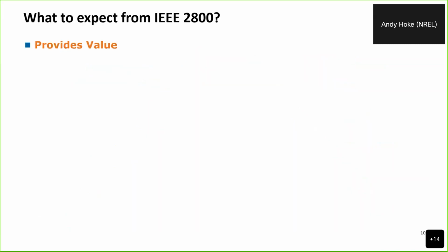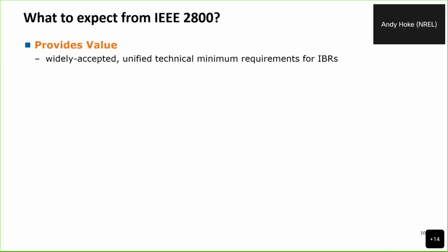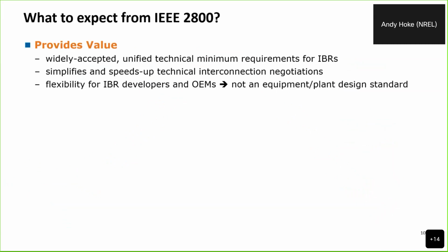Okay, so what do we expect from IEEE 2800? What kind of value do we expect to get from it? I mentioned that we get hopefully widely accepted unified technical minimum requirements for inverter-based resources, and we hope that that will speed up the interconnection of those resources. The standard was designed to provide those requirements, but provide them so that you comply at the point of measurement of the plant, rather than looking inside the plant and telling you what the plant needs to look like on the inside. So in other words, it's not an equipment design standard or a plant design standard. It provides the flexibility for a developer to design a plant however they want, as long as they meet the basic requirements of interconnection of IEEE 2800. This is the same philosophy followed in 1547 that has been successful for many years.